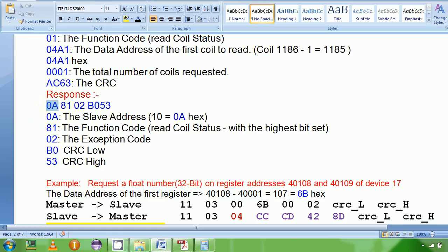And while the master, the PLC, is sending these bytes to the SCADA, HMI, or your laptop, it will assemble all these bytes and do CRC16 over it. B0 is the lower byte and 53 is the higher byte.